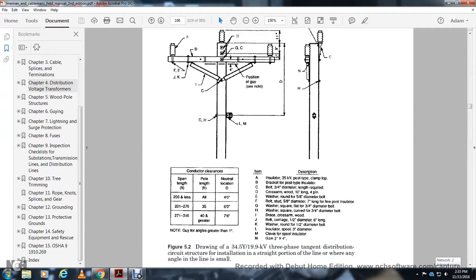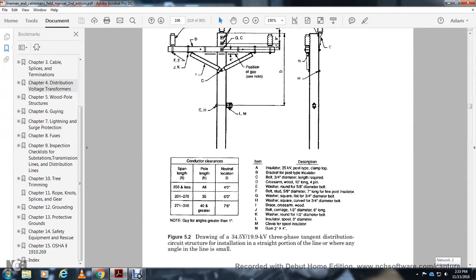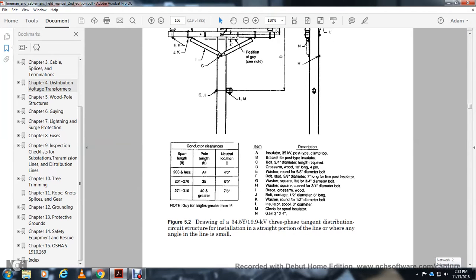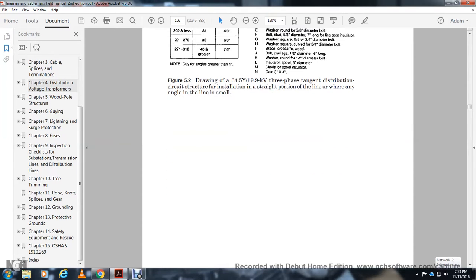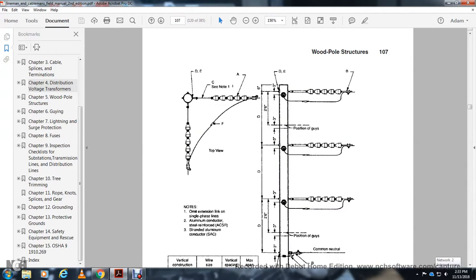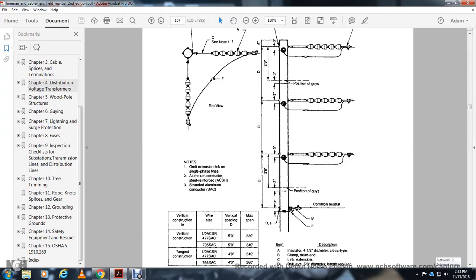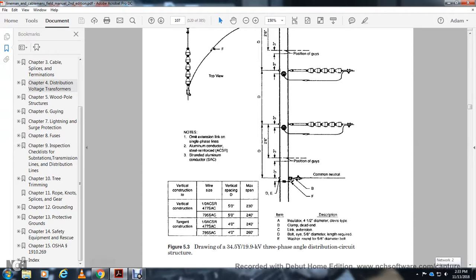Drawing of a 34.5Y/19.9-kV three-phase tangent distribution circuit structure for straight portions of line where angle is small. Another drawing shows 34.5Y/19.9-kV three-phase angle distribution circuit, vertical construction tangent construction with wire size, vertical spacing, and maximum span specifications. Position of guys shown in degrees.